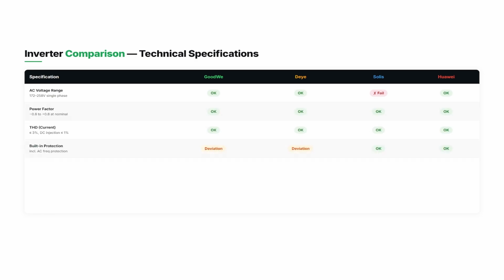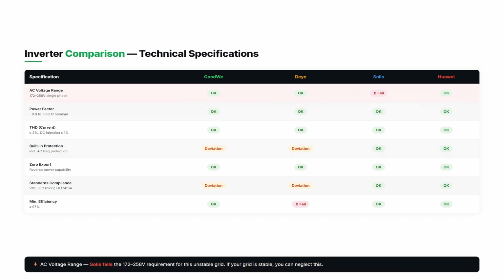As the project is located in an area with unstable grid voltage, it was required that inverters should operate from 25% below nominal voltage up to 12.5% more than nominal voltage, which for single phase would be 172 up to 258 volts. Solis can't fulfill this requirement, however, others claim they can. If you have stable grid voltage, then you can neglect this.